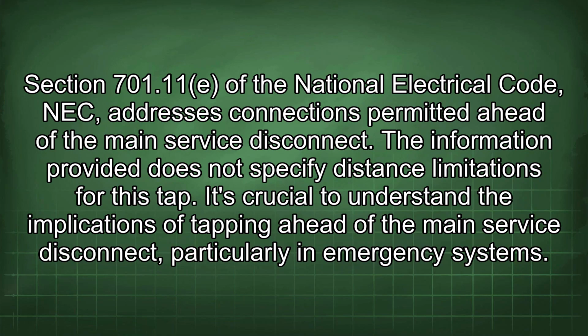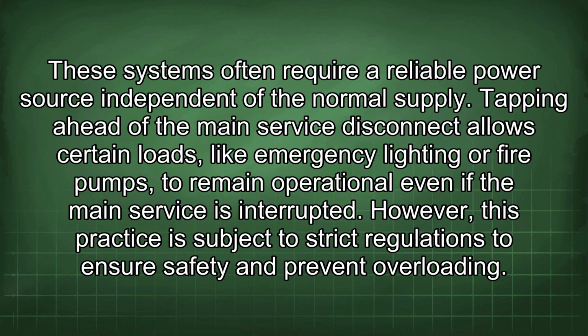Section 701.11 of the National Electrical Code, NEC, addresses connections permitted ahead of the main service disconnect. The information provided does not specify distance limitations for this tap. It's crucial to understand the implications of tapping ahead of the main service disconnect, particularly in emergency systems. These systems often require a reliable power source independent of the normal supply.